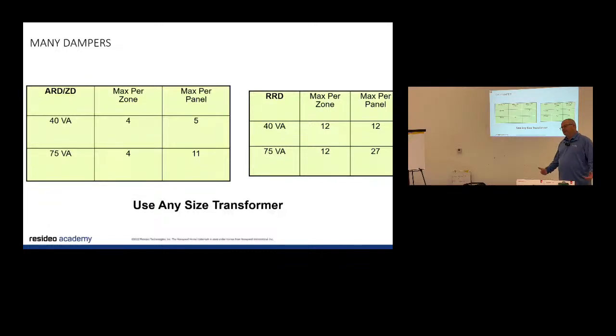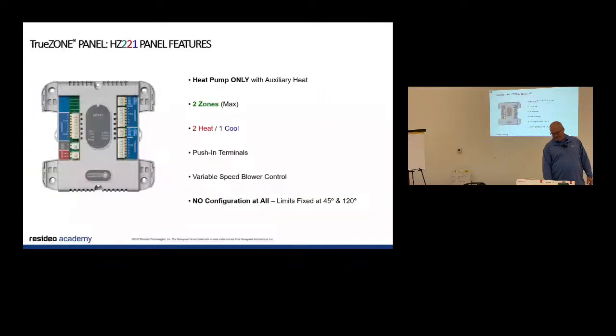Okay, so generally guys are doing this during new construction, but there is a huge opportunity to do it after the fact. If you've got a walkout basement, it's even more of a necessity. That whole wall that's exposed, you know, it's one thing to be in a basement that's all concrete, you've got quite a bit of insulation value there. If it's an exposed basement and they're not zoning, they're going to zone, or they're going to have a cold basement, one or the other. Clear?